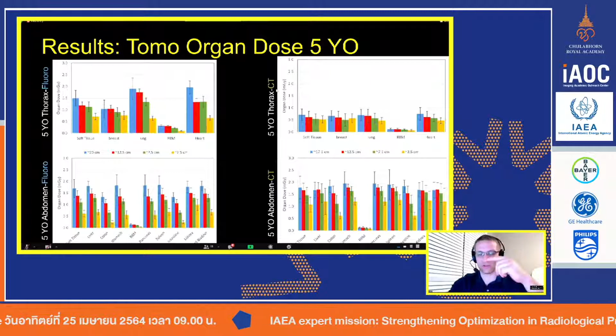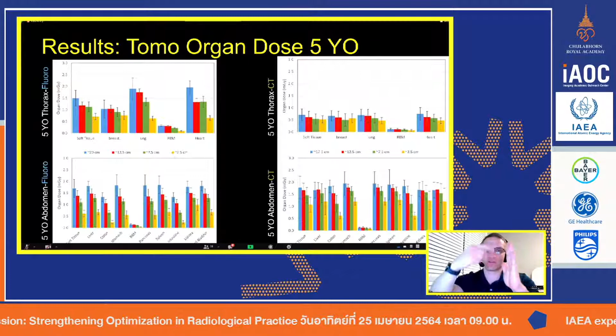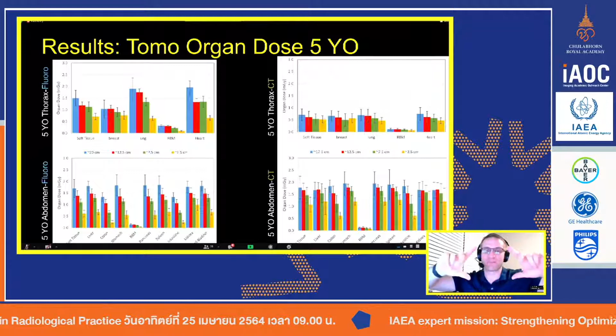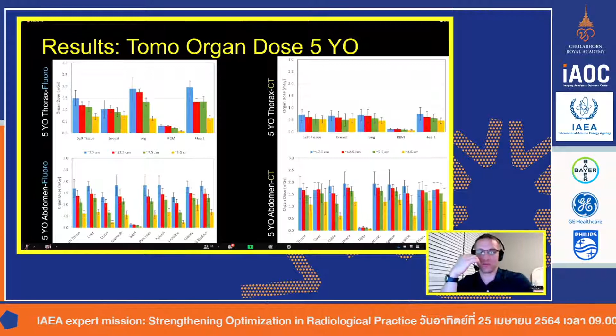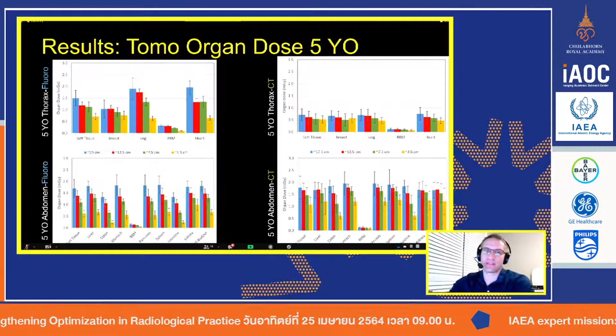So this is where you see that the CT itself, when you do just the normal helical scan of, say, the chest or the abdomen pelvis, is generally pretty low. The reason is the tube current modulation, which we talked about many weeks ago. When the C-arm spins around the body, it does modulate. Every angle will be a different mA, but the difference is the field of view is this big, versus on CT it's teeny, only a couple millimeters wide. So the CT scanner can modulate much, much better. That said, the doses are getting much better. They're much more equivalent today.